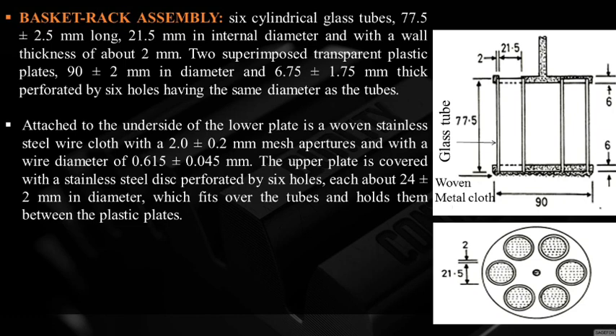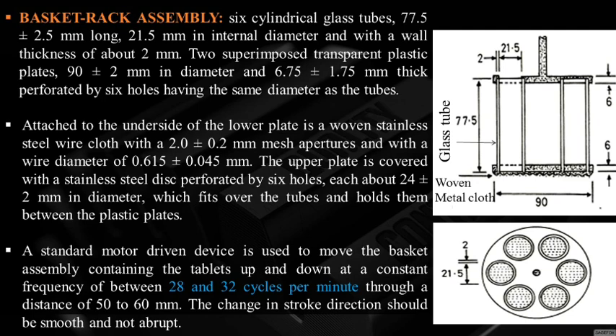The upper plate is covered with a stainless steel disc perforated by six holes each about 24 ± 2 mm in diameter, which fits over the tubes and holds them between the plastic plates. A standard motor driving device moves the basket assembly up and down at a constant frequency of 28 to 32 cycles per minute through a distance of 50 to 60 mm; the change in stroke direction should be smooth and not abrupt.